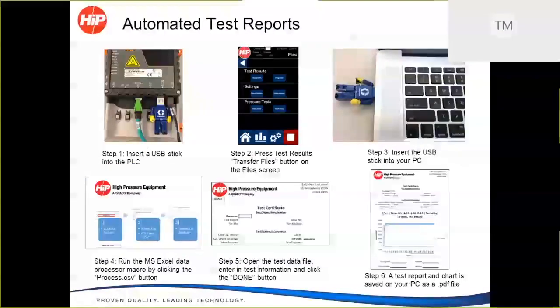You can then put that USB stick into your computer. We provide an Excel-based program, an automated macro, on a USB stick with the unit. You can run that Excel file, and there'll be one button on there that says process the files. You can push that button and it'll pop up a window to ask you to select the file based on the date and time of the test that you want to run, and it'll open up the file. This will still be in Microsoft Excel. You can enter a few critical things about your test, for example, your customer name, the name of the test, the part number, things of that nature. Then when you hit the done button, it'll generate a PDF copy that shows your certification, your information about your part, and your pressure versus time data. The operator can sign off that test, and subsequent pages of this report will be all the Excel-based data for pressure versus time.